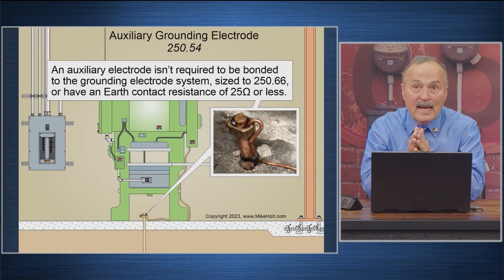No, they didn't. The reason they have it, as Brian was saying, is that people kept submitting public inputs to give requirements to ground rods that are not required. And inspectors were actually trying to enforce requirements on ground rods that are not required. So by putting in a rule saying there are no requirements, the inspectors can't require you to do something that's not required. And it solves the problem of every code cycle submitting to Panel 5, hey, you should be requiring this. I'm like, no, we already say it's not required. So we're done. We have a requirement telling you don't have to comply for those people that think you're supposed to. Brian? We have a similar type of rule with burial depth on the bonding jumper, and we're going to get into that one.